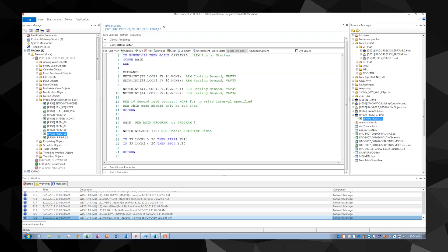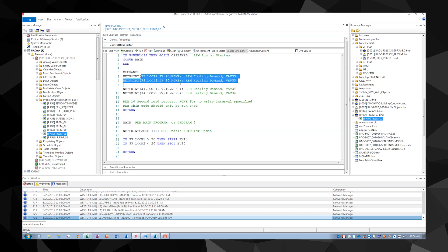Let's look at a different way we can write similar code using the NetPoint command. At first glance, this code may seem more complex, but ultimately it may help speed up your controller operation. This routine will grab the present value of each point we want to request, namely the loop values from VAVs 33 and 34, every 10 seconds. Every 10 seconds, the cache in the controller will update automatically, reducing the time needed to execute the Control Basic program.